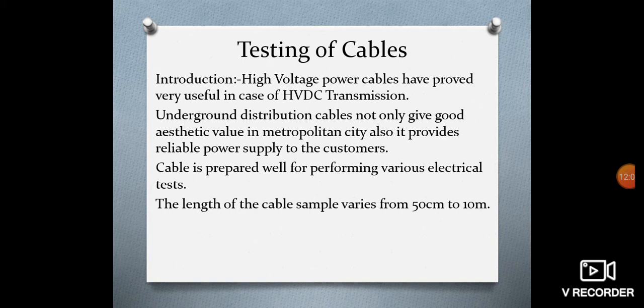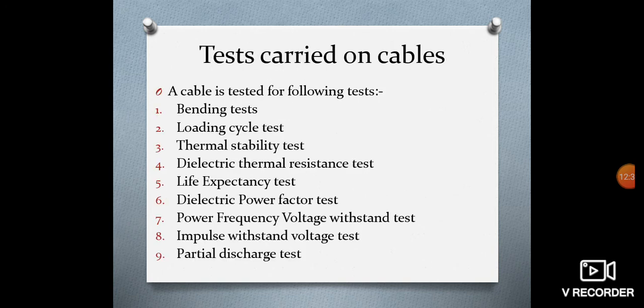High voltage power cables have proved very useful in case of HVDC transmission. Underground distribution cables not only give good aesthetic value in metropolitan cities, but also provide reliable power supply to the customers. Cable is prepared well for performing various electrical tests. The length of the cable sample varies from 50 centimeters to 10 meters. The tests carried out on cables are bending tests, loading cycle test, thermal stability test, dielectric thermal resistance test, life expectancy test, dielectric power factor test, power frequency voltage withstand test, impulse withstand voltage test, partial discharge test. So one by one we'll understand the tests carried out on cables.